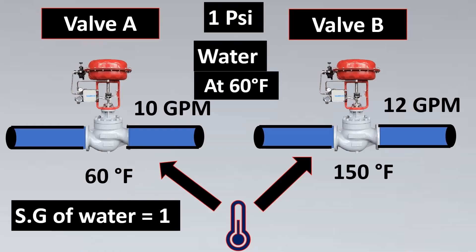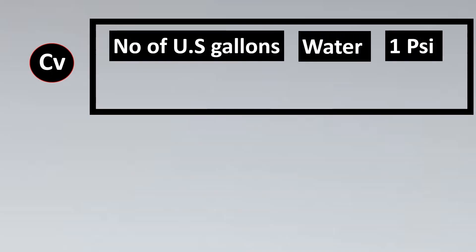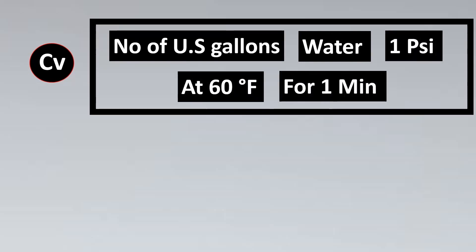So we have three standard parameters: a pressure drop of 1 PSI, water as the fluid, and a temperature of 60°F. With that, the definition of CV is as follows: CV is the number of US gallons of water that can flow through a valve with 1 PSI pressure drop at 60°F for 1 minute. This is the definition of CV.